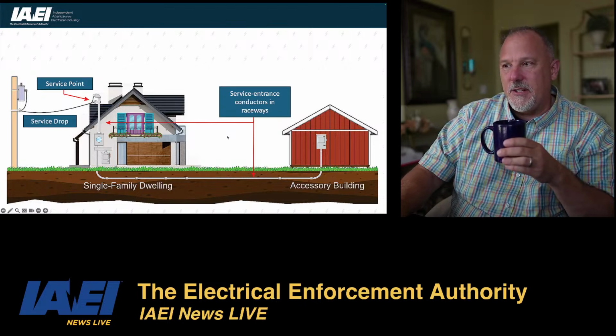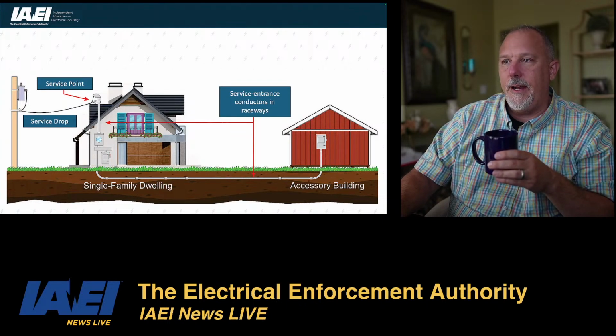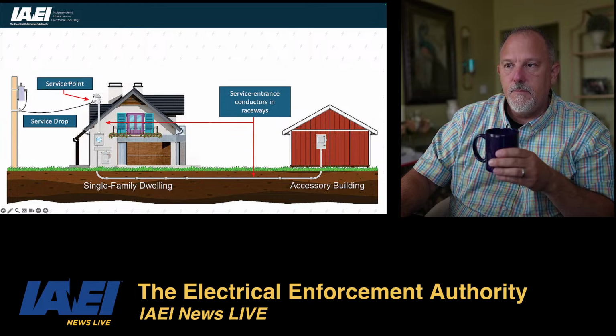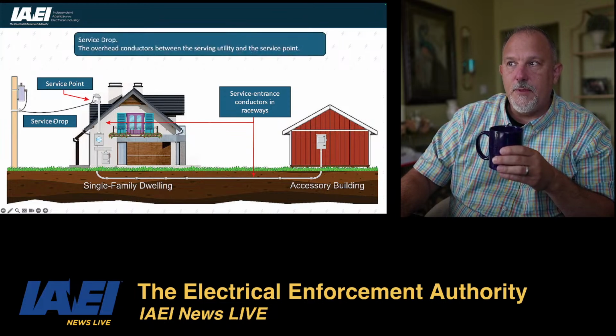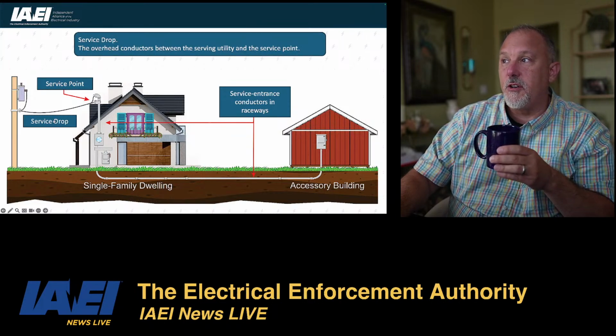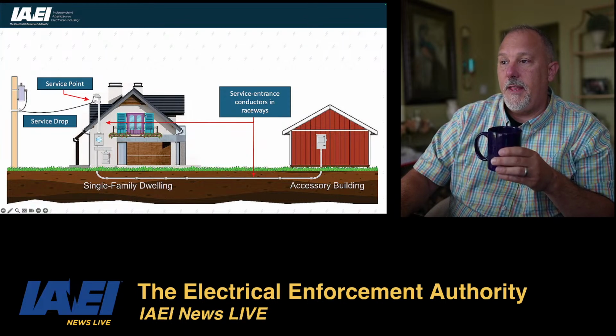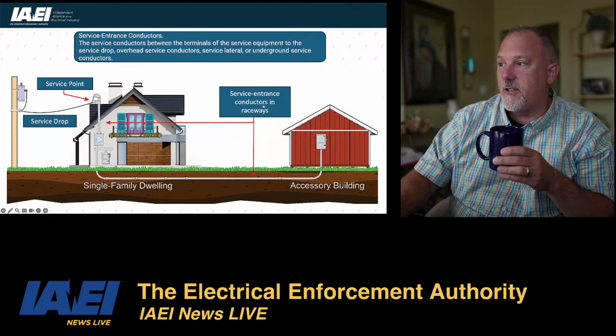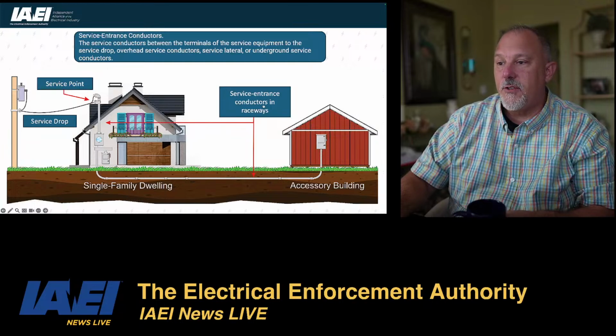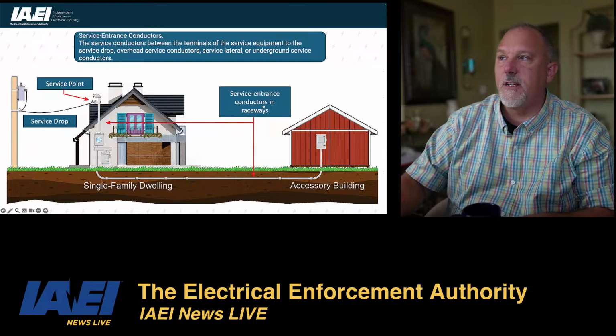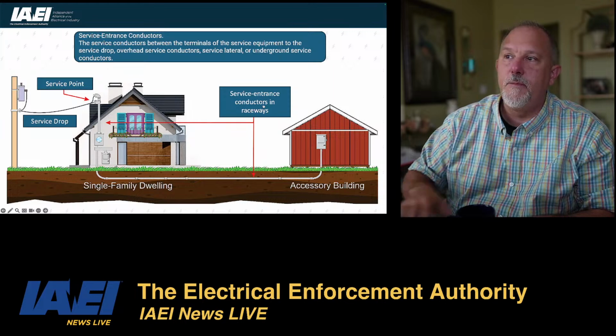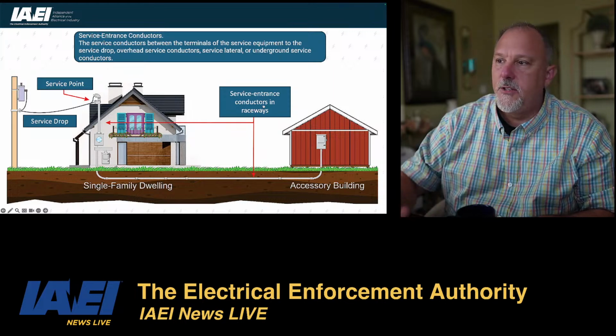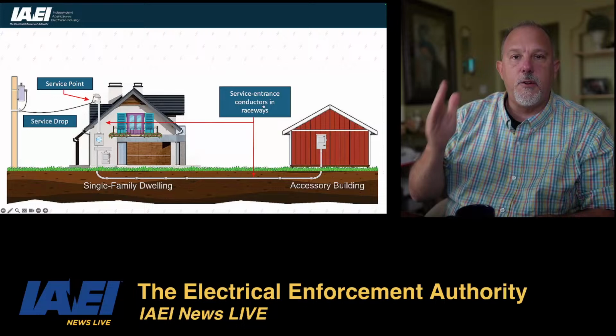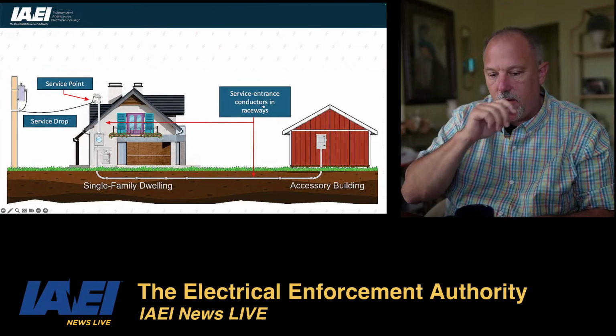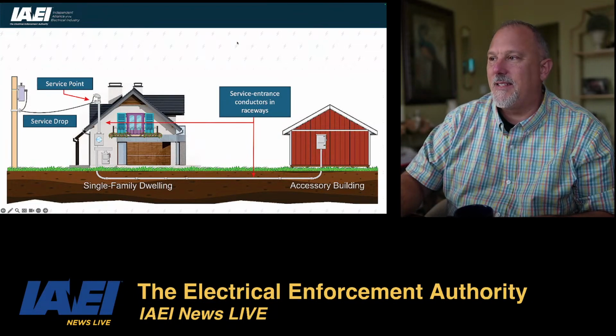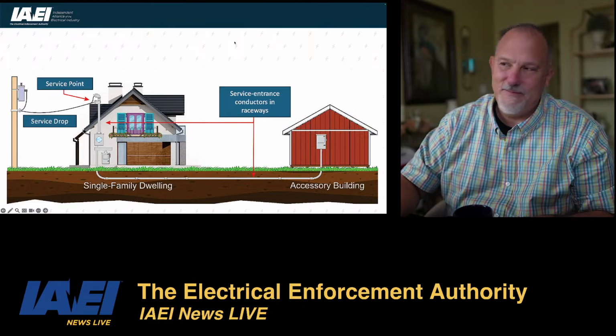So here's just another diagram, another great IAEI diagram. You have your service point. You have your service drop, the overhead conductors between the serving utility and the service point. And these are your service entrance conductors in raceway. A service entrance conductor is the service conductors between the terminals of the service equipment to the service drop, and so on. So it's very important to understand terminology and to be able to identify all the pieces of pie. Yummy fudge.